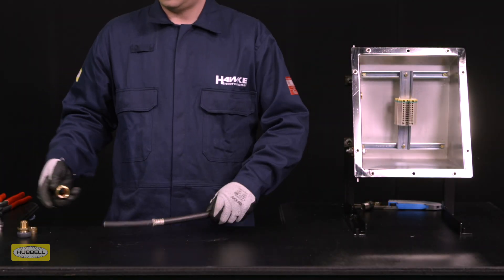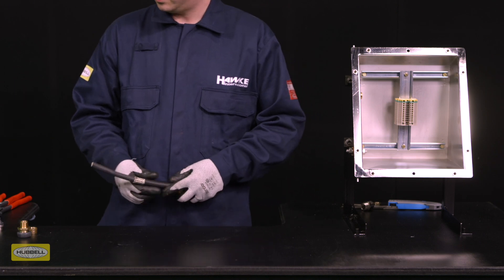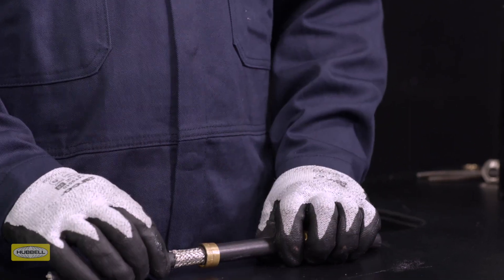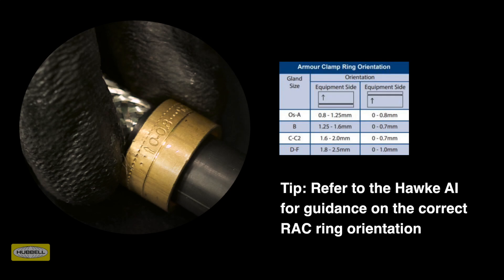Slide the back nut, middle nut, and armour clamping ring onto the cable. Ensure that the orientation of the reversible armour clamping ring is correct, with the arrowhead indicating the correct armour, braid, or tape pointing to the equipment. Always refer to the Hawke assembly instructions for guidance on the correct armour clamping ring orientation.